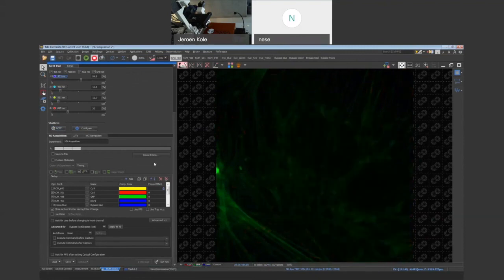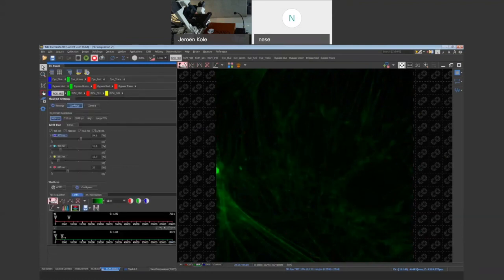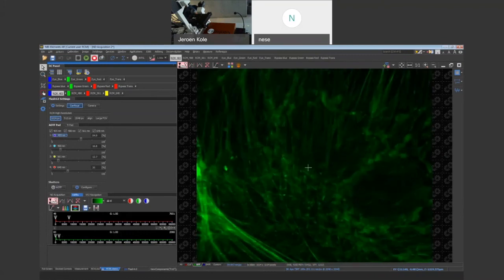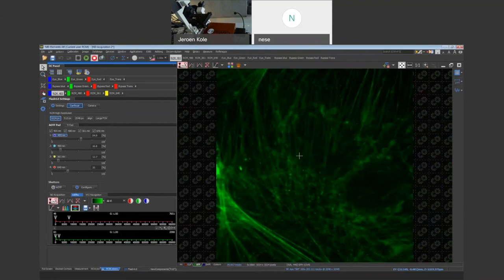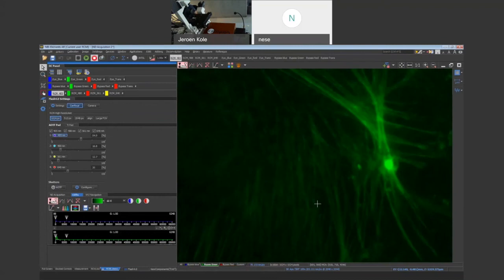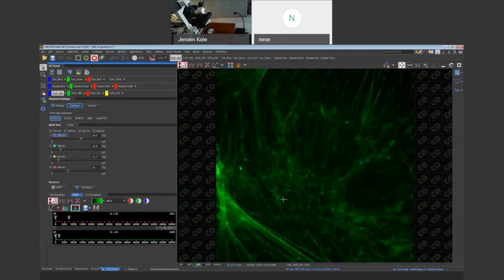As you can see, this is more up close because the RCM's view is not as big as the view of the widefield. But here we see some nice fine structure, especially in the actin channel. And if I look at my widefield, well, I hope you agree, I'm not really able to resolve the fine structure here, much better in this image. And this is just the added lateral resolution that the system gives you.